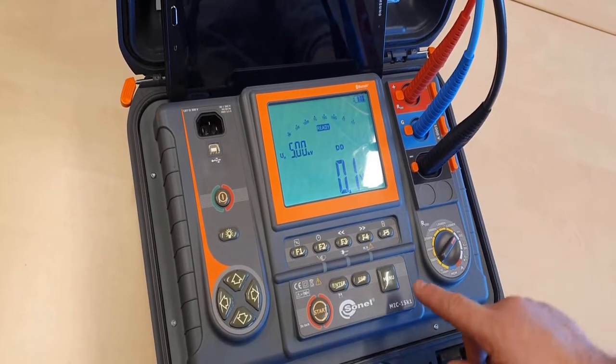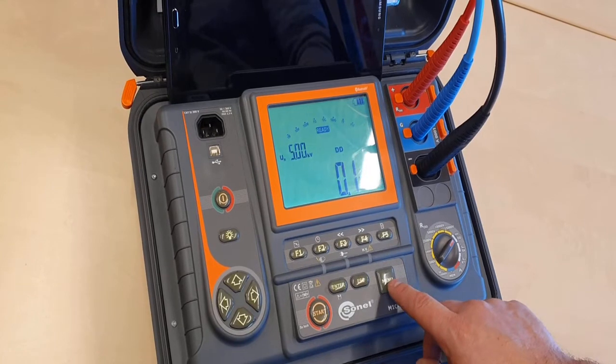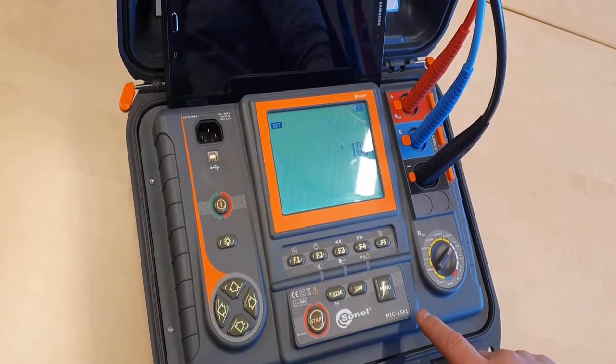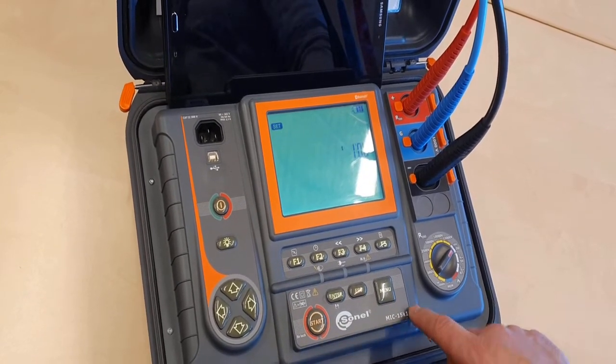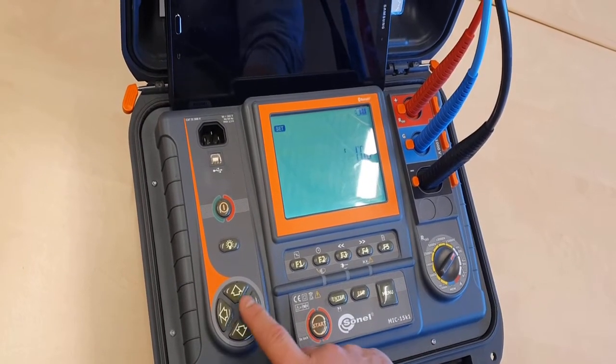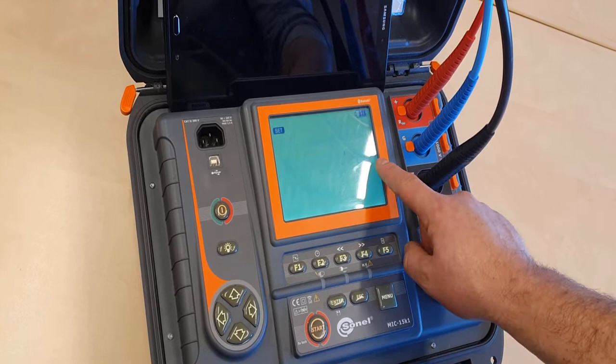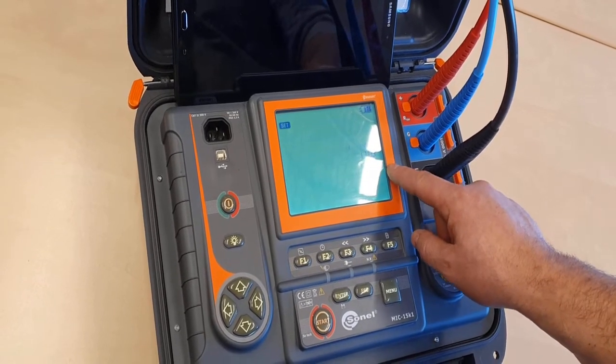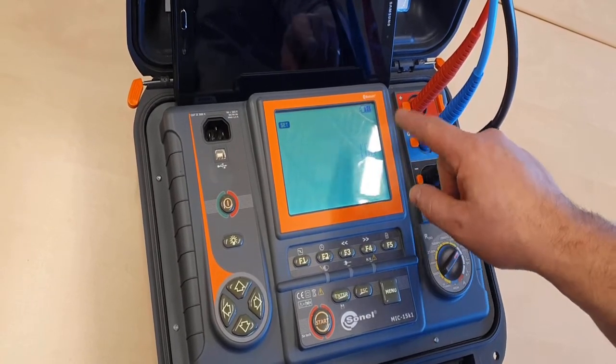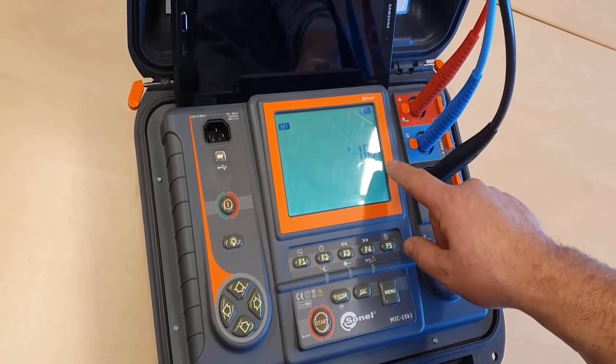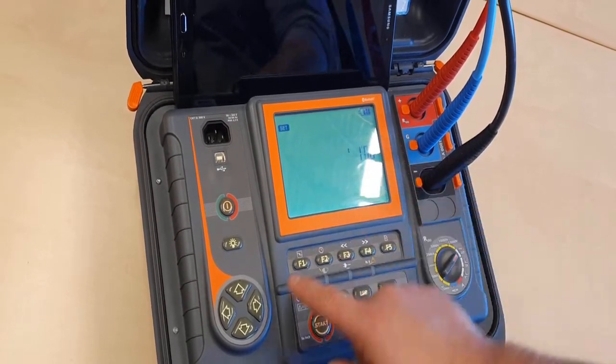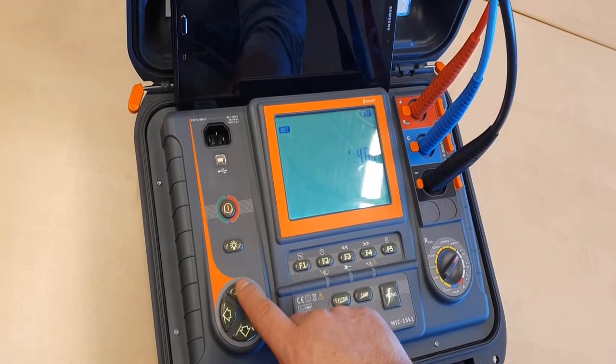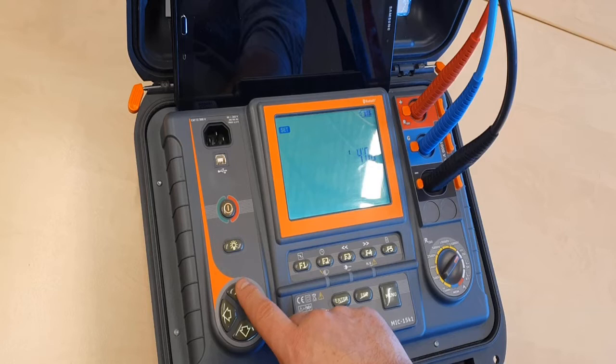But before we start measurement, I am pressing MENU button. I need to set the measurement time to set as before in the DD setting, which I set before 5 minutes. For the purpose of this movie, I put 5 minutes, but generally, the rule is the more the better. Such PDC measurements sometimes take up to several hours. It depends on how large the object is.